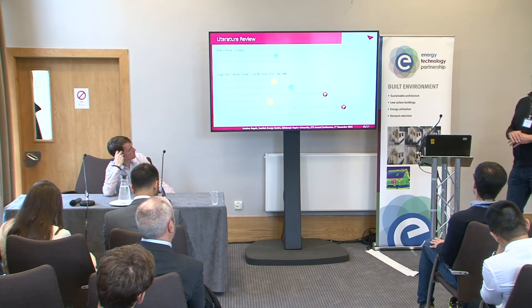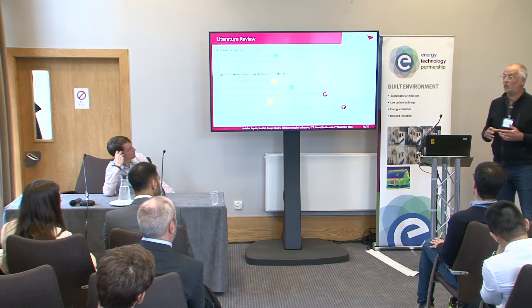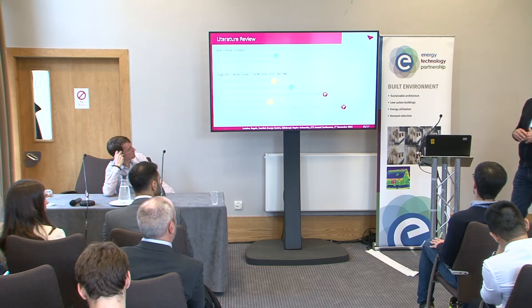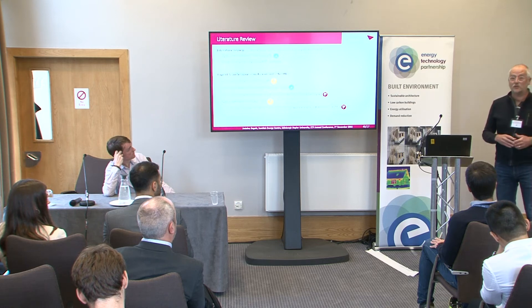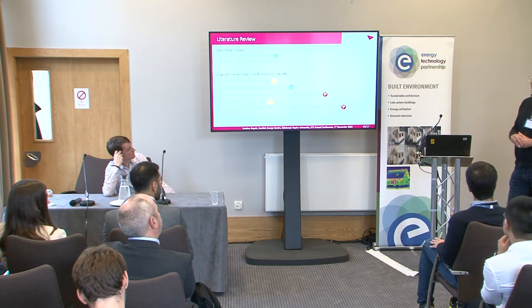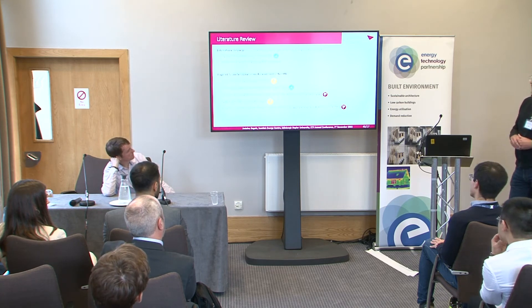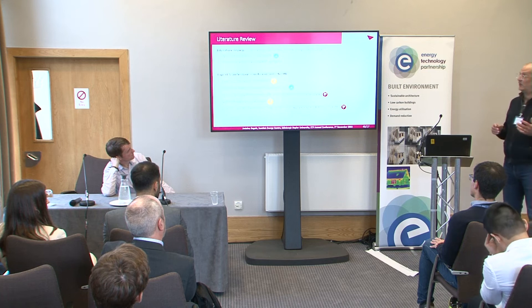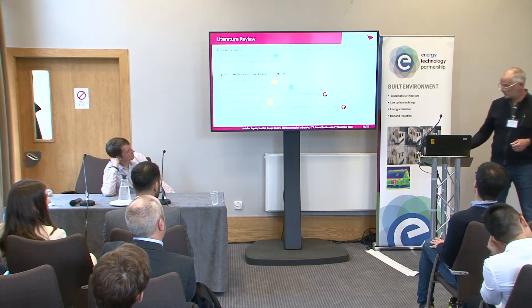There's not that much publication for UK buildings. The oversizing of the heating system in the UK is likely to be quite significant, which is good. However, UK buildings usually perform quite poorly compared to Denmark and Sweden — first, because it's the oldest building stock in Europe, and there is quite a significant performance gap. We use night setback when we need to move towards continuous heating, and policies differ — Sweden has limited flow temperature in the 80s.